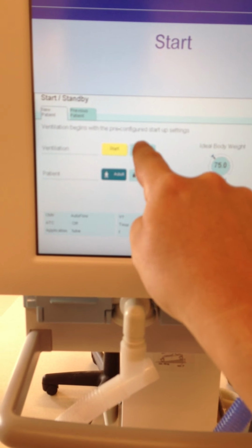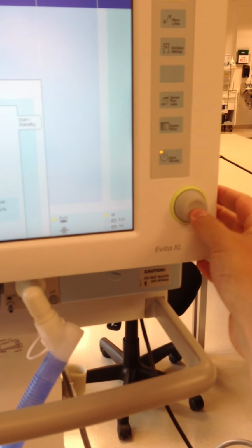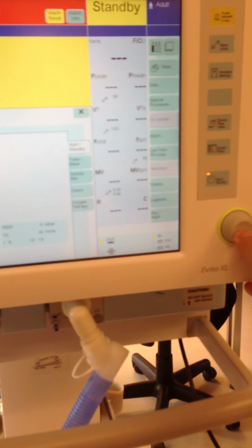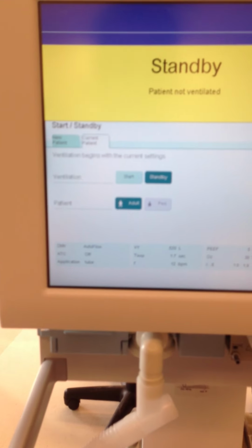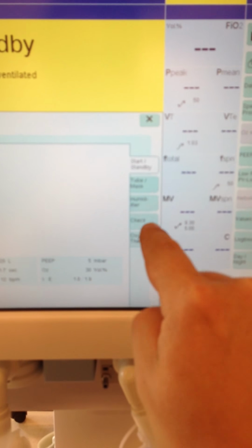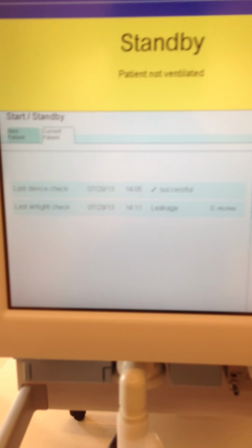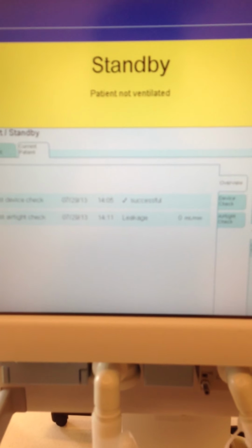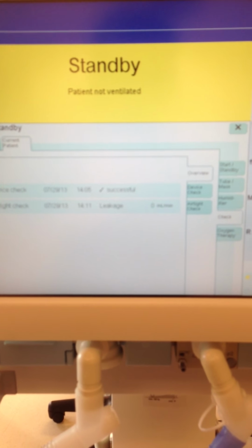So first thing we're going to do is go into standby. You're going to select that. We can reset our alarms so it doesn't bug us. And on the side menu or side tab here, we're going to go down to check. Alright, so it shows you the last device checks and how they were, if there's any problems with them. What we're going to do is go over here to device check.